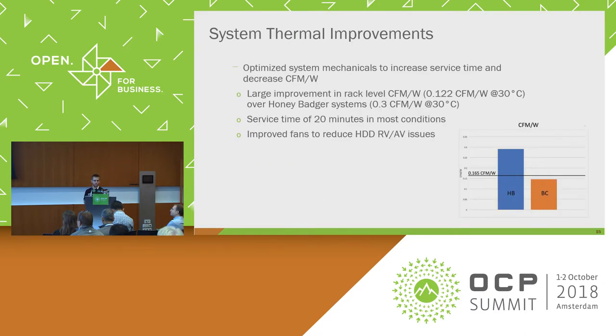For system thermal improvements compared to our previous chassis, we went from about 0.3 CFM per watt at 30 degrees Celsius down to 0.122 CFM per watt at the rack level — a huge decrease in CFM requirements to cool the system as a whole. This allows us to deploy more racks and need less cooling in the data center.